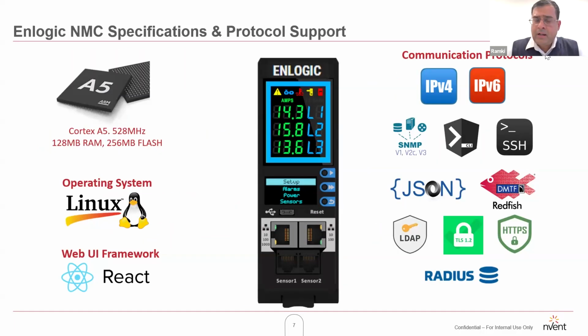The other important aspect of any PDU is its compatibility or interface. The Enlogic PDUs work on what we call an open system. You do not need any particular software to communicate with the PDU. We provide standard communication protocols—SNMP, HTTPS—and also new APIs like JSON, Redfish, etc. This means the Enlogic PDUs are very compatible with any existing system you may have, which is an important feature that will help you choose a total solution.